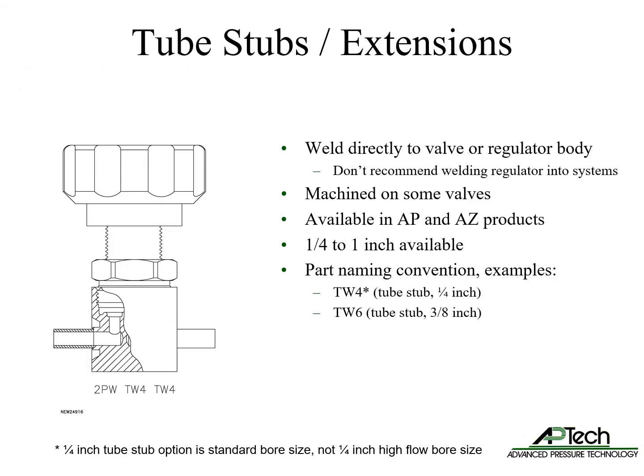Welded tube stubs or tubing extensions are standard connection options for the AP and AZ-series valves and regulators; however, we don't recommend welding regulators into gas systems. Some valves feature machined tube stubs. Tube stubs are available in 1/4 to 1 inch sizes. The part naming convention is TW for tube followed by the size, such as 4 for 1/4 inch. 1/4 inch stubs are true 1/4 inch bore size, not HF size.